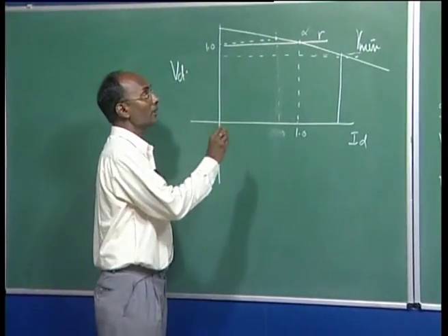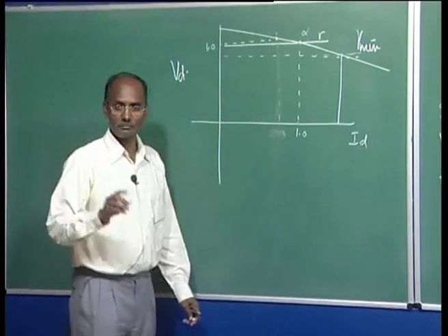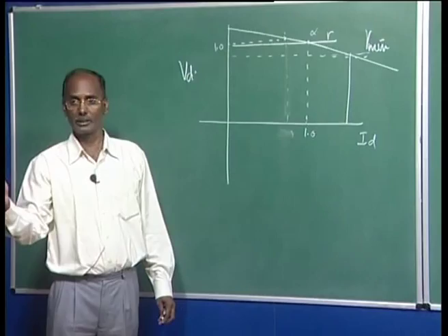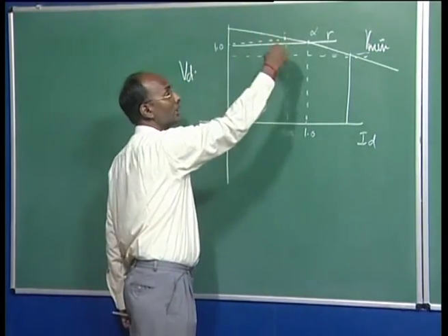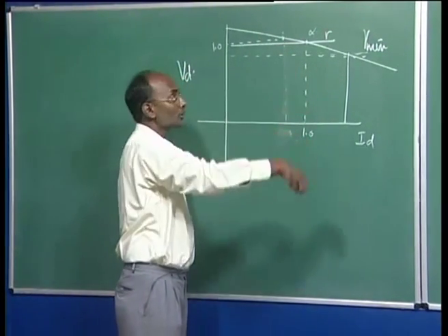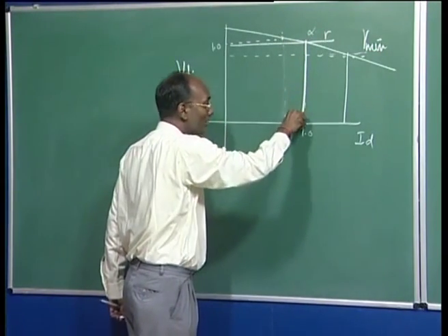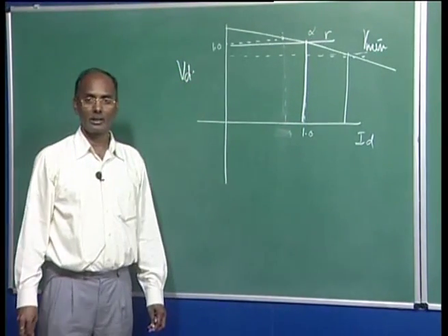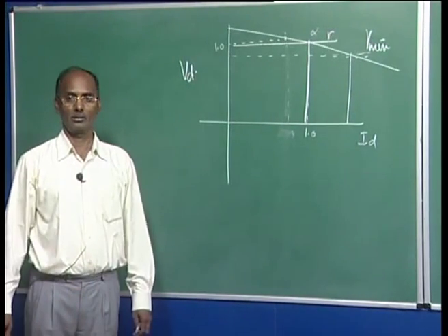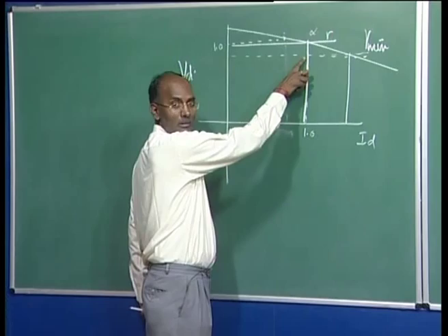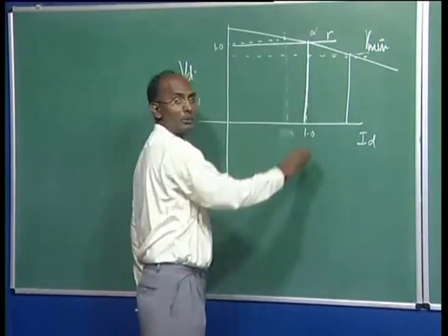So it is believed that we should operate the rectifier end to control the current, so that it should not increase, by changing alpha or changing the VDO. So in this characteristic, we want that this rectifier end should control the current. Now even though this voltage has gone down, your new operating point is this.